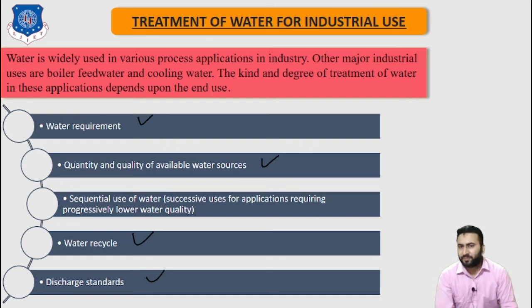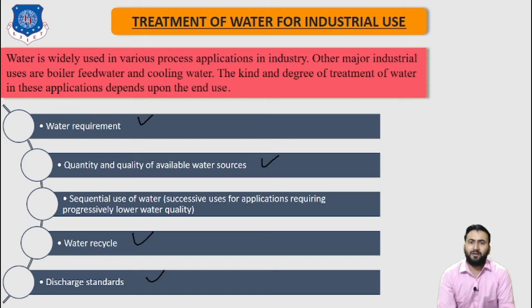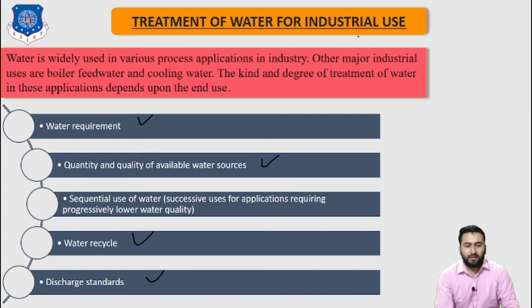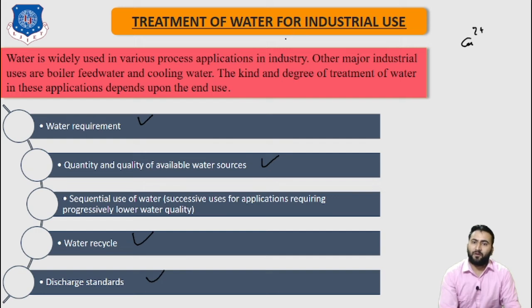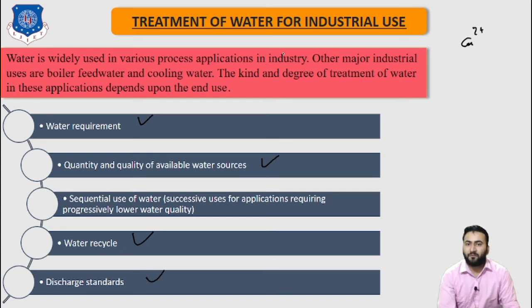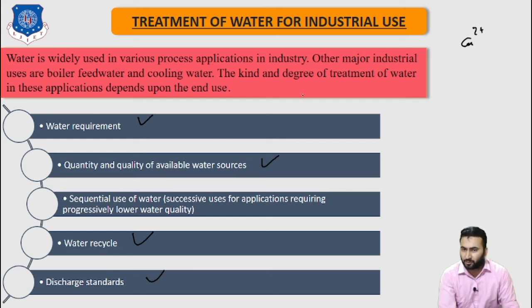Now let us discuss about internal treatment. Internal treatment is designed to modify the properties of water for specific applications. Examples of internal treatment include: reduction of dissolved oxygen with sodium sulfite; addition of chelating agents to react with Ca²⁺ (hardness) and prevent calcium deposits; addition of scale inhibitors to disperse scale; addition of inhibitors to prevent corrosion; addition of chemicals to adjust pH; and use of disinfectants for food processing to prevent bacterial growth.